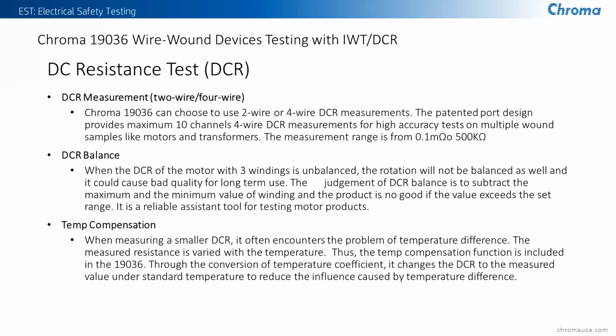This tells you accurately that you have the proper wire gauge and that there aren't any shorted turns within the windings. It can also be used for DC resistance balance measurements, especially on motors. Imbalanced windings or different turns can definitely cause some winding anomalies that cause an imbalance in a stator. With the added temperature probe on this one, it also gives you the more accurate capability of measuring the resistance at different temperature levels to ensure proper compensation at those different temperatures.